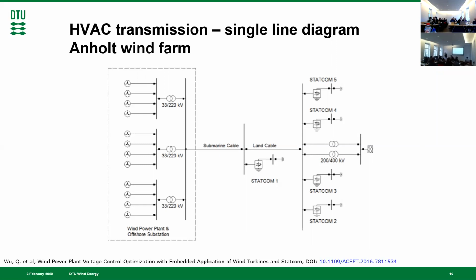STATCOMs are also power electronic devices, from a helicopter view rather similar to the power electronics inside the wind turbines. They're used to provide reactive power compensation for the submarine cable, and to meet the requirements from the grid code. So again, a lot of equipment inside the wind farm impacts its stability, operation and control, coming from the grid side.